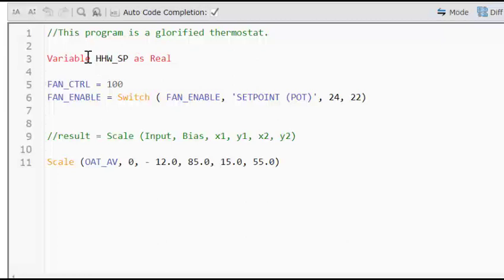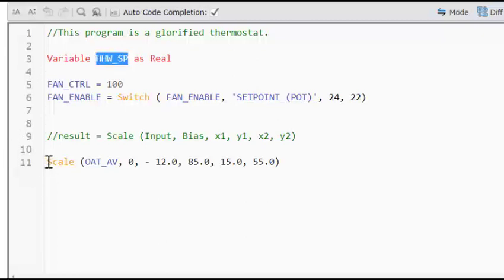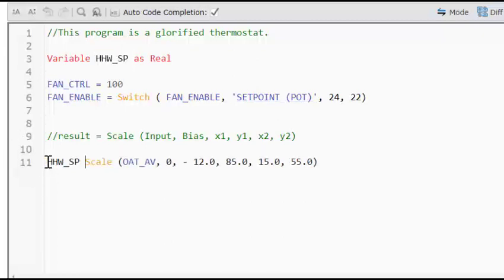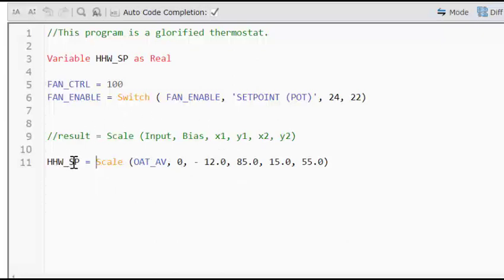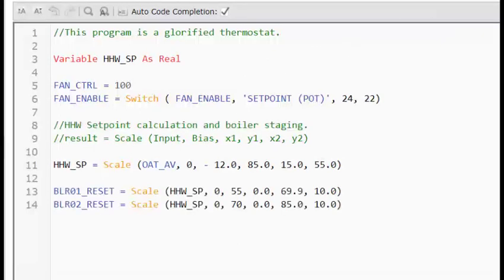So basically I have to say as real. And now I have a placeholder to receive the information or the calculation from our scale function. So I'm just going to simply copy and paste it so I get my syntax correct. And now as scale function gets executed, whatever calculation it makes, that number is going to be put into heating hot water underscore set point variable. We can now reference this calculated value throughout the program.